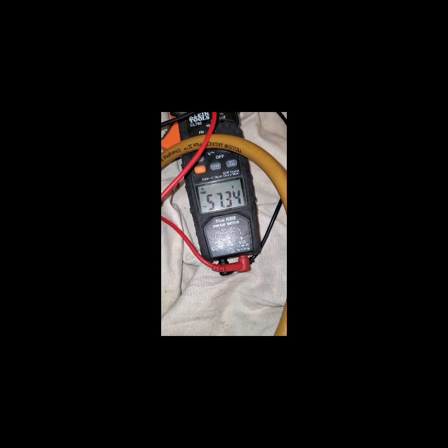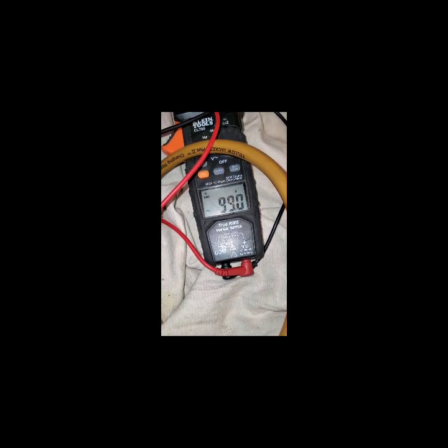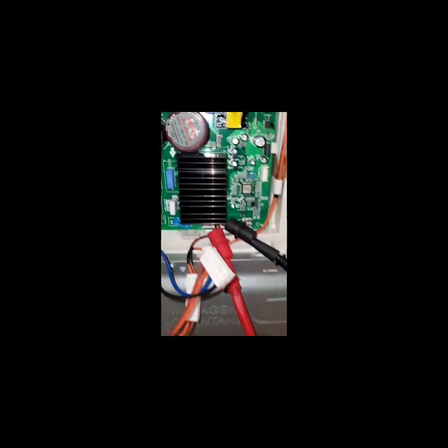I got everything hooked up. It's been about 30 seconds so I went ahead and I pressed the test button. Now watch what happens with my volts here. We're gonna count about 30 seconds to see if this thing actually achieves the 200 volts that the tech sheet stated that it should read. It just shot up to about 102, 103. So far so good. Just monitoring everything, making sure we got everything hooked up good.